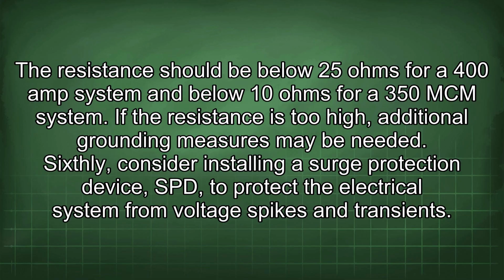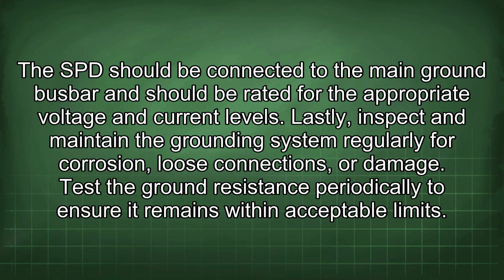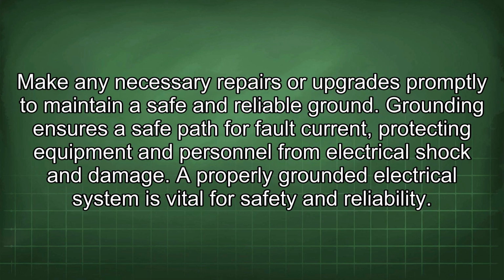Sixthly, consider installing a surge protection device, SPD, to protect the electrical system from voltage spikes and transients. The SPD should be connected to the main ground busbar and should be rated for the appropriate voltage and current levels. Lastly, inspect and maintain the grounding system regularly for corrosion, loose connections, or damage. Test the ground resistance periodically to ensure it remains within acceptable limits. Make any necessary repairs or upgrades promptly to maintain a safe and reliable ground.